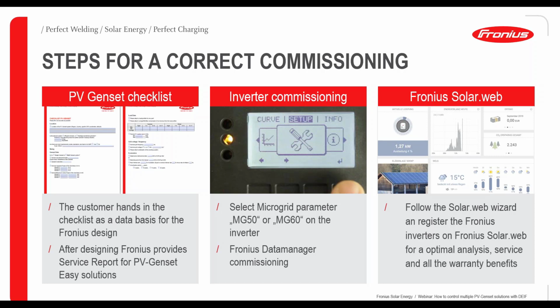microgrid parameter. So by installing it, there is the point where we can set then microgrid 50 or 60 Hertz. This we need to do. And then there is the option to commission the data manager, of course, which we saw earlier by this Modbus communication. By following the Solar Web Wizard, so commissioning the data manager is in this case the same as the Solar Web Wizard. By following the Solar Web Wizard, we can also bring the system online.